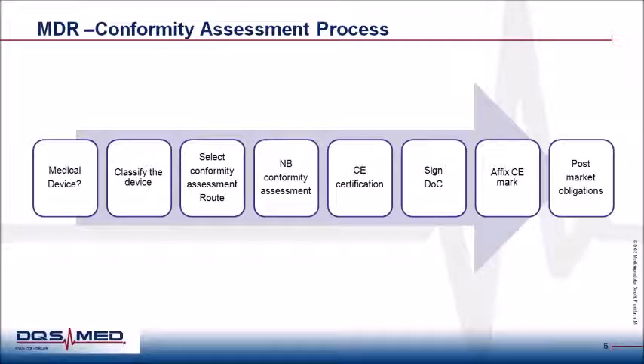If yes, then the notified body will review your technical file, perform an audit, and lastly, you will be given a CE certification. Once you have a CE certification, you need to sign the declaration of conformity, affix a CE mark, and you're good to go to market your product. But just marketing the product does not end your responsibility. You also have to meet the post-market obligations. The same holds true with MDR. Everything remains the same as it is with the existing medical device directive. Only here the post-market obligations have been strengthened a little more.